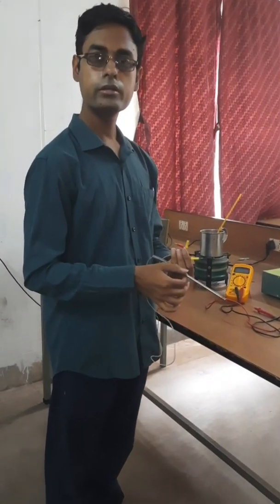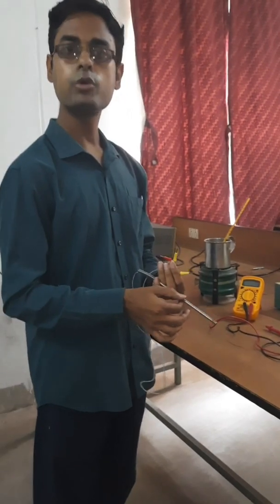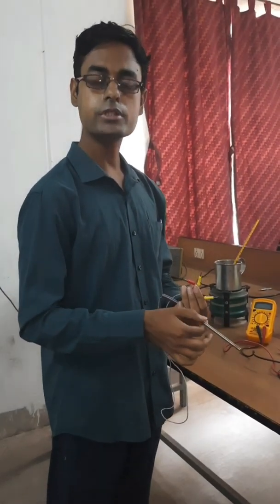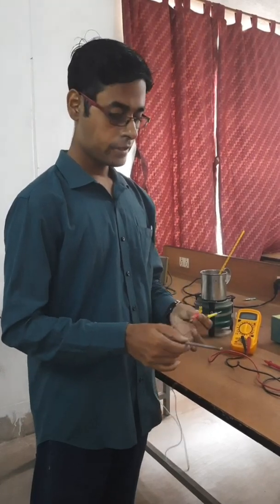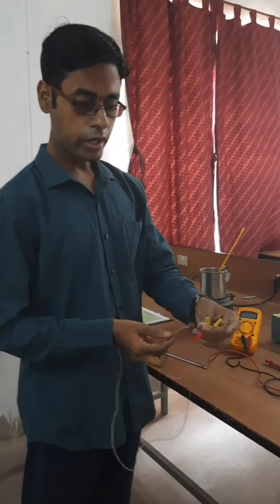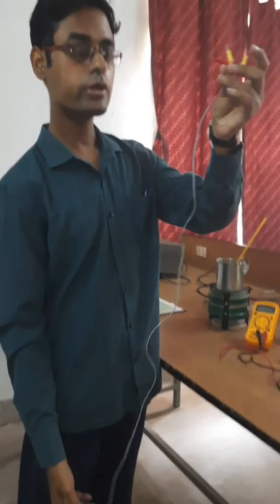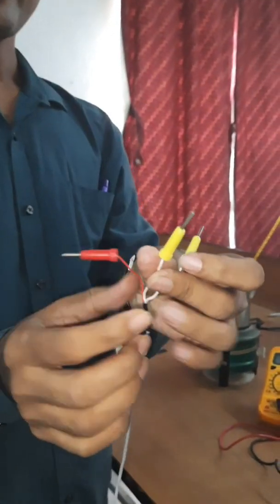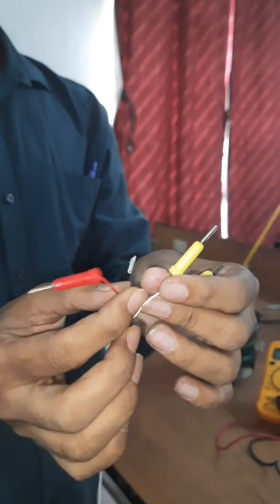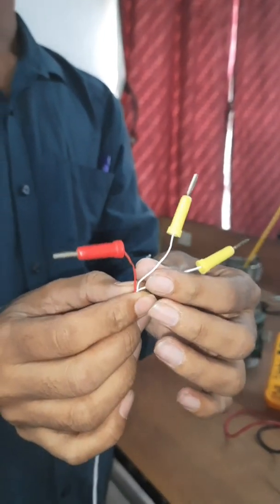This is the RTD element which is inside this thermowell. This thermowell is made of stainless steel. The RTD element is PT100. You will find that this is a 3-wire RTD. The connection all the way through comes out to be a 3-wire RTD. Here one of the wires is red, the other two are white color.